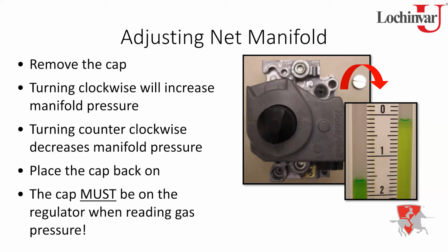Now, if the unit was running, the unit's going to say, hey, we were running, we lost the flame signal, so let's go back and try to relight. You've got a little bit of time here, so you go through a post-purge period, then you're going to go through a pre-purge period again. That gives you about 40 seconds to make your adjustment and get that screw cap back on before it lights.